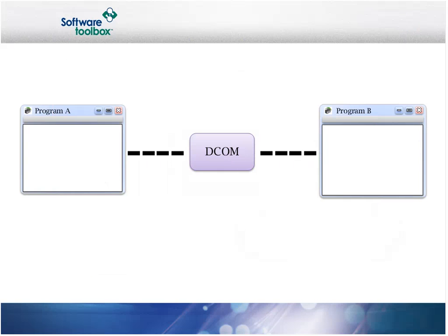So what are blocking calls? In software developer terms, a blocking call is when one program asks another program to do something, and the requesting program sits and waits on the remote program to respond, thus blocking all activity on the requesting application, including the user interface interaction, until that call completes. All OPC function calls are, by their nature, blocking calls. The client or server will wait on the other to respond to a call. This applies whether you're doing reads, writes, or subscriptions with your OPC-based system.